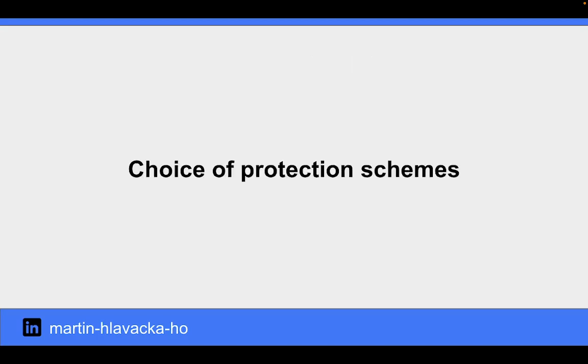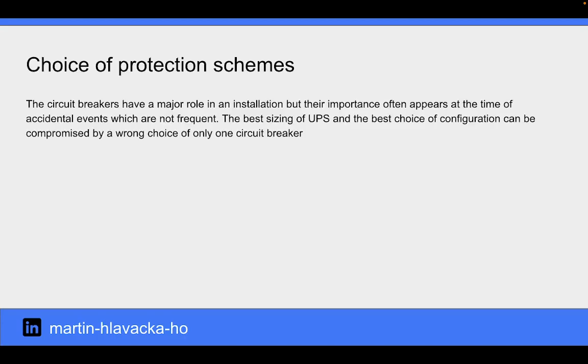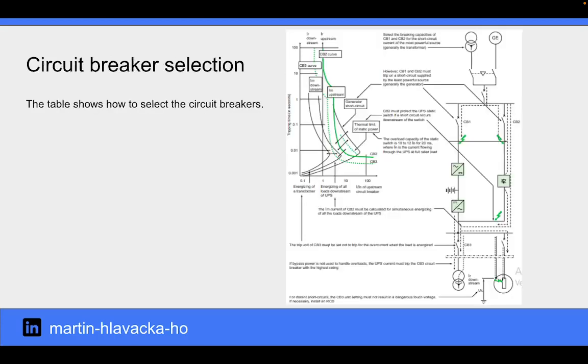Choice of protection schemes. The circuit breakers have a major role in installation, but their importance often appears at the time of accidental events that are not frequent. The best sizing of UPS and the best choice of configuration can be compromised by a wrong choice of only one circuit breaker. The graph here shows how circuit breakers are submitted to a variety of situations.